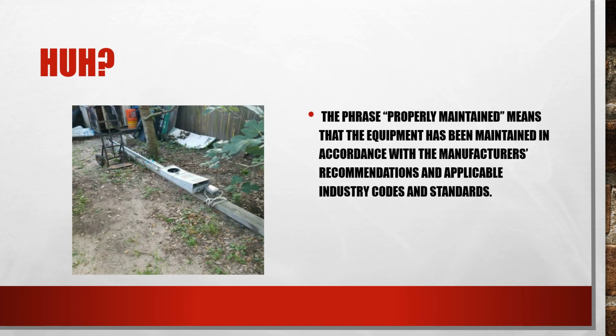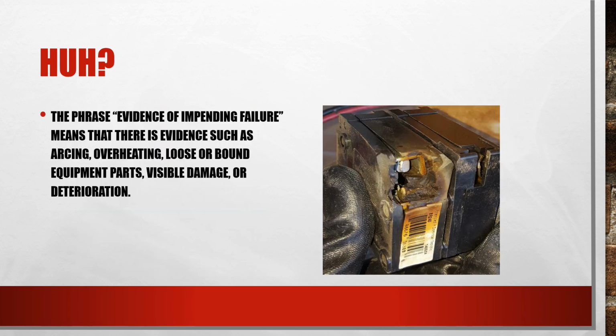The phrase properly maintained means that the equipment has been maintained in accordance with the manufacturer's recommendations and applicable industry codes and standards. So this doesn't look like it's being properly stored or maintained, but some standards for this include a NEMA recommended practice for electrical equipment maintenance, another NEMA standard, evaluating water damaged electrical equipment, and an IEEE standard, life expectancy of molded case circuit breakers. So it is our responsibility now to make sure that these are in good shape whenever we do choose to reuse them.